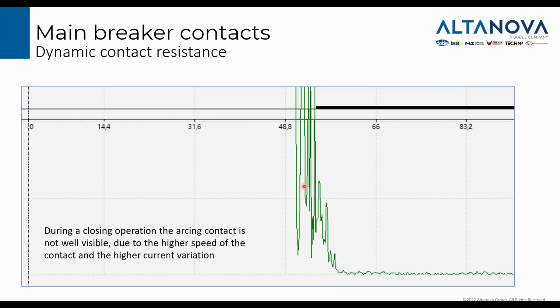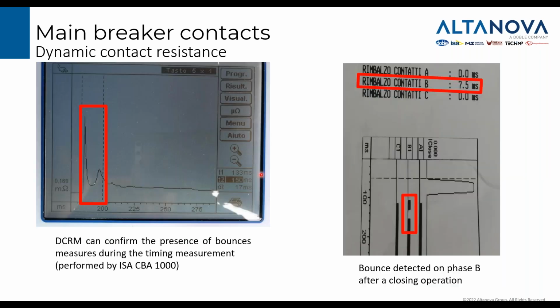The speed will not help to have clear graphs, and also you are applying a higher current change, because you are going from a situation where the current flow is, let's say, 0, then the contacts start to close, and then you go from 0 to the maximum, and this for sure introduces some noise in your measurement. So if you want to check the status of the arcing contact, it's better to do the test during an open operation.